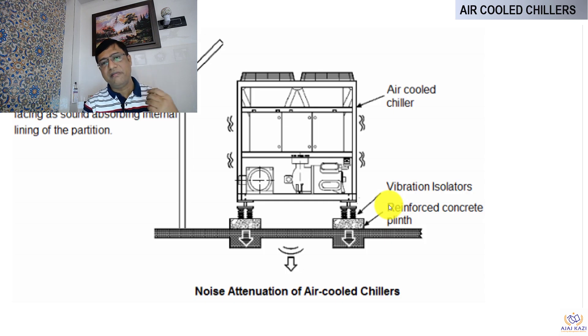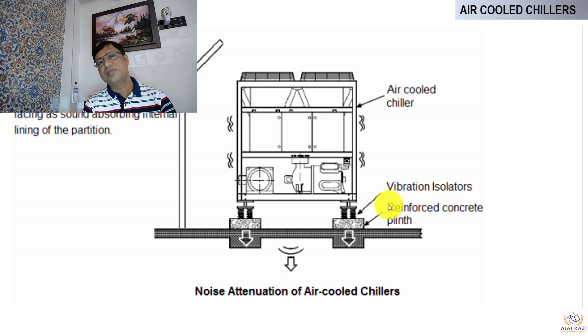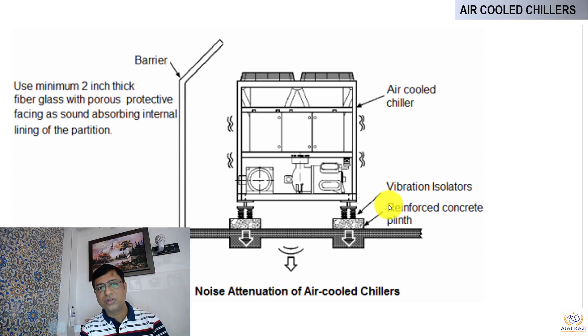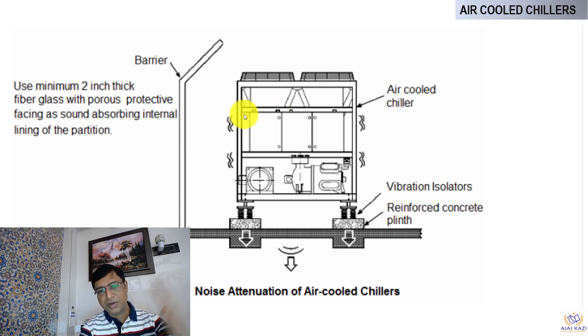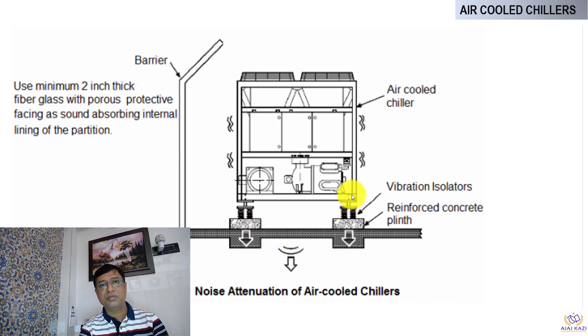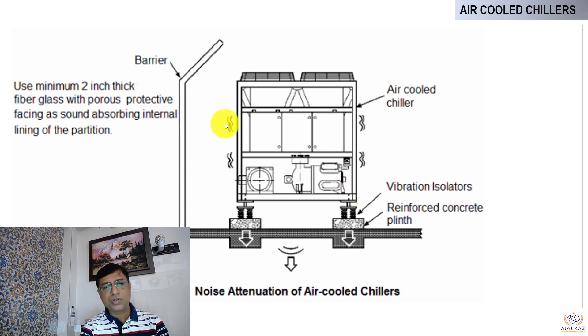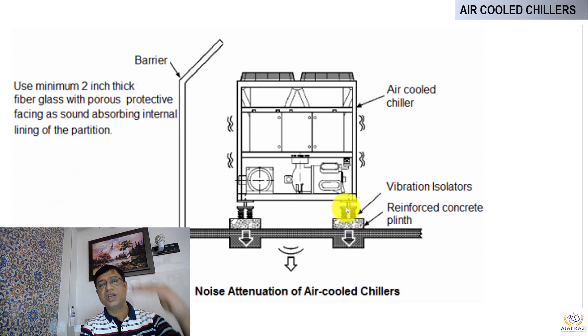It is very important to know that air-cooled chillers will have noise, and if there are sensitive areas near the chillers it is important to create a barrier so that the noise can be reduced — it cannot be eliminated, but it can be reduced. The third important thing is the vibration coming from the chillers. Because there are many rotating elements — fans and compressors — vibration can travel down to your structure. That is why vibration isolators play an important role; they can reduce or dampen some amount of vibration.